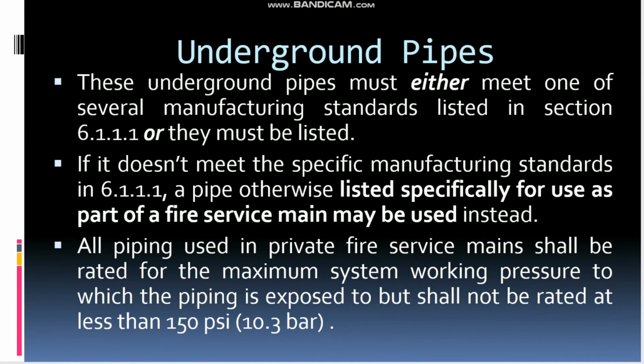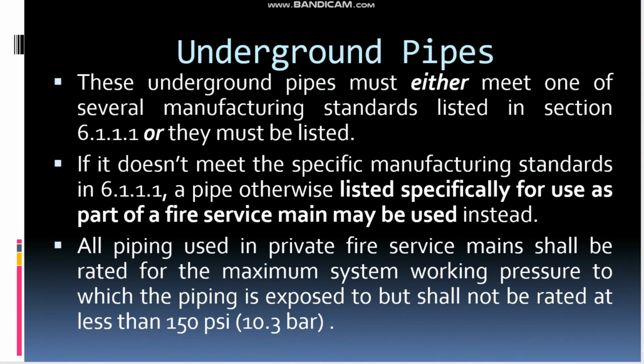The answer to this question is, for these underground pipes, we need to follow the standard as mentioned in this table. If that is not possible, then this pipe must be listed by a third party. And the second thing, if it is listed, it should be listed specifically for use as part of the fire service main. This should be listed mainly as a fire service main.